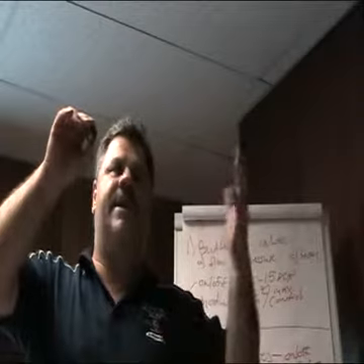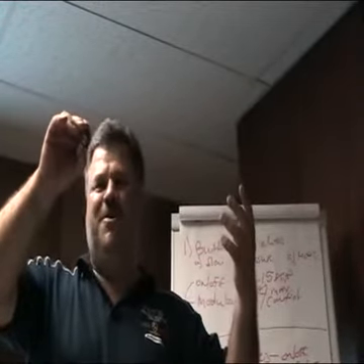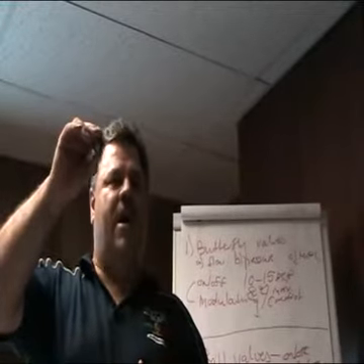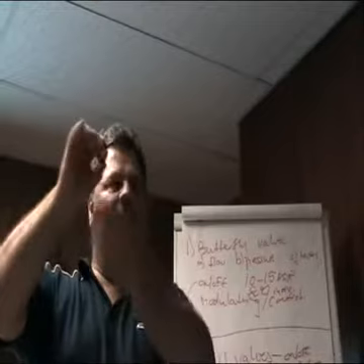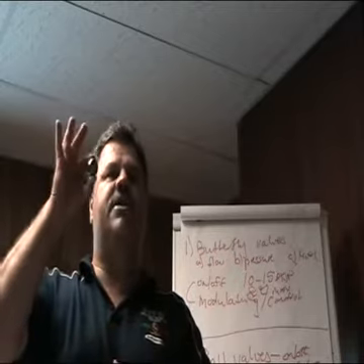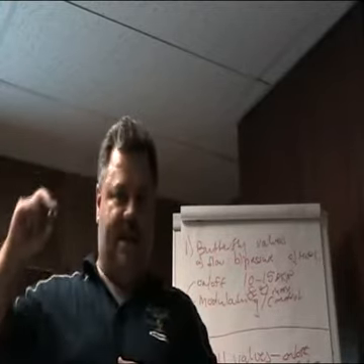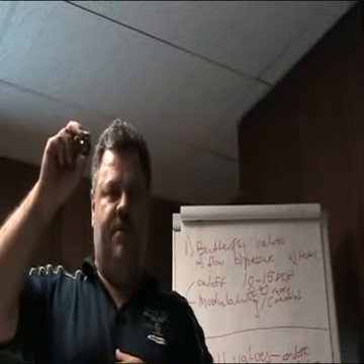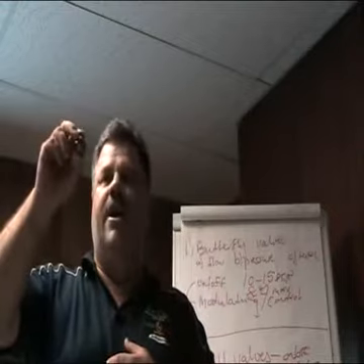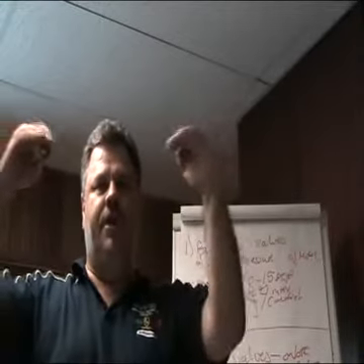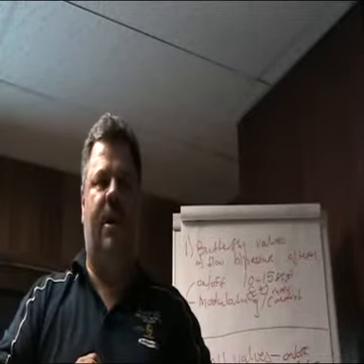Let's say the flow that you can get through this valve is 100 cubic meters per hour on 100 mil. When this valve opens, you will pass exactly the same that the pipe can pass through this valve. That's full bore, because it's the same size as the line size. When you get reduced bore, this valve will have, for instance, a 3-inch ball in it, so it's a smaller hole. It's like a venturi, like an orifice, that's it. Okay, everybody okay with that? I don't want to be too complicated on this.